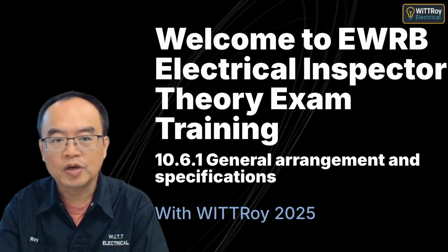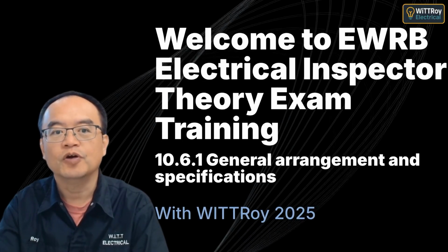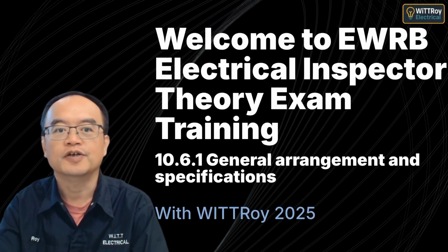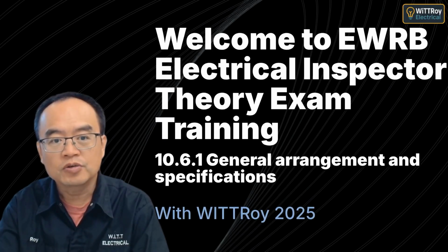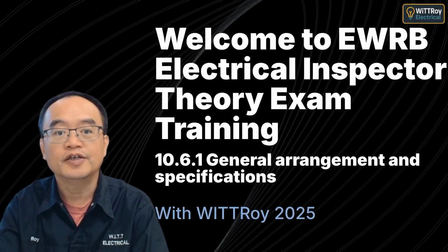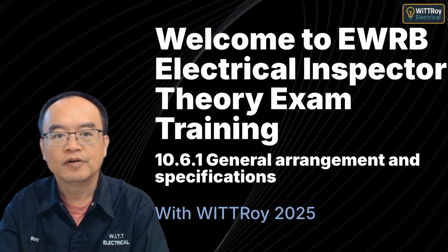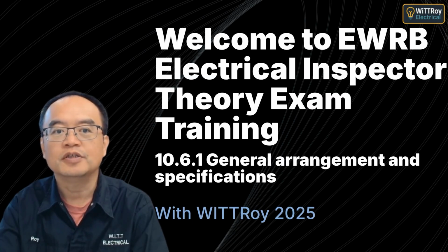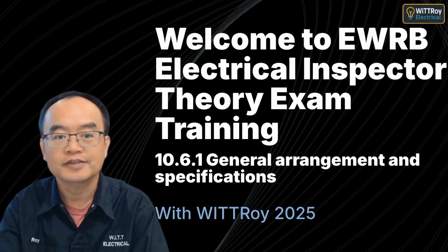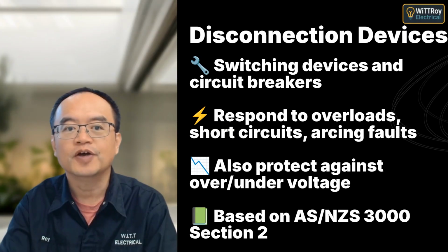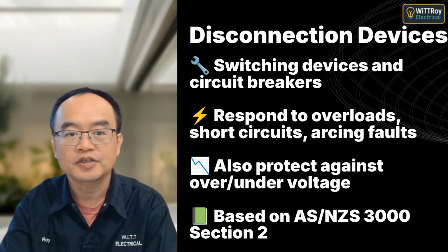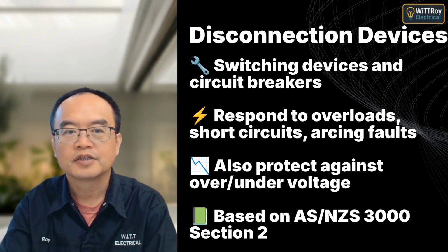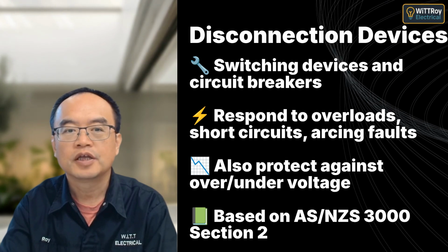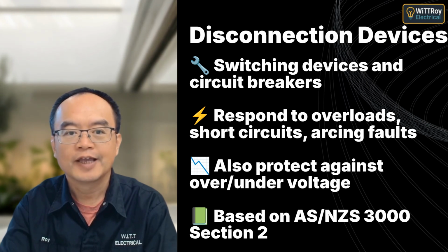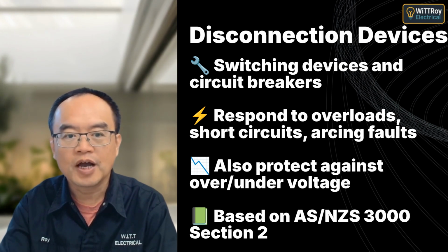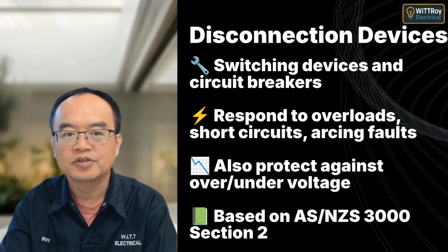Hi everyone, I'm Whitroy. In this short lesson, we're focusing on general arrangements and specifications, especially how to select and apply protection devices that keep installations safe from overcurrent, short circuits, and voltage irregularities. Protective devices like MCBs, RCDs, AFDDs, and fuses must automatically disconnect the supply under overload, short circuit, earth leakage, or arcing faults. AS/NZS 3000 Section 2 outlines the minimum requirements for these essential safety functions.